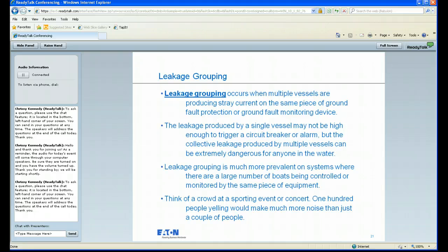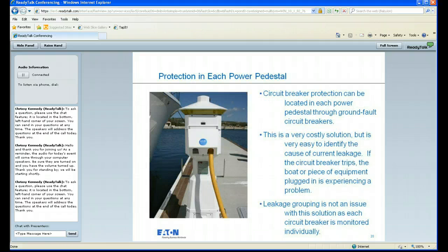Chris, this is Gary again. Can you explain, or maybe this is something for ABYC, if a vessel or a boat has the neutral and grounds bonded together within their system, will the ground fault monitoring alarm in that state, because there will be a parallel path for neutral currents and an imbalance between the neutral and the hot leg? That's not an instance that I'm fully aware of. Kevin or Chuck Devitt, Captain David Rifkin, those guys are probably more suited to field that question than I would be.